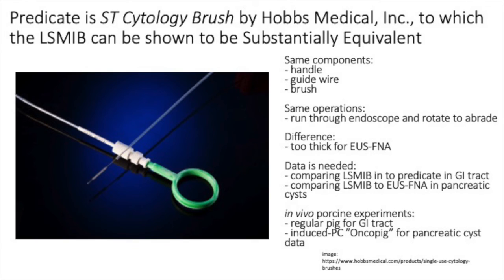This brush consists of the same basic three components: a handle connected to a guide wire and a guide wire connected to a brush. Both the device and the predicate undergo the same mechanical operations as well. They are run through the endoscope, rotated, and used to brush some sort of epithelial surface. The principal difference is that the ST cytology brush is too thick for EUS FNA. Accordingly, safety and efficacy data comparing the LSMIB to the predicate to determine substantial equivalency needs to be performed first in the GI tract alone.